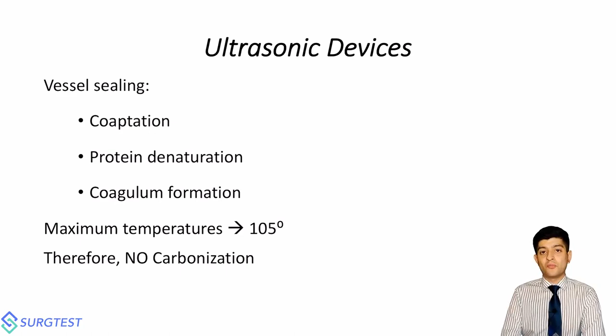In ultrasonic devices, the maximum temperatures that are reached are just beyond boiling point, so close to 105 degrees. So you never end up having carbonization or very strong eschar formation within these ultrasonic devices. That being said, you do end up having some amount of sticky soft tissue that gets caught within the active jaw of these devices that needs to be cleaned, but it is not the same eschar that you will see in monopolar and bipolar energy.